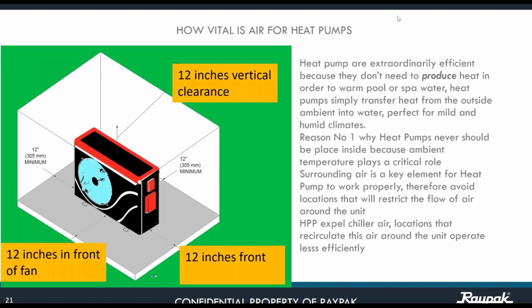Okay. On the air side, the description shown right here, guys, does not mean that the unit has to be inside of a cube, inside of a room. It's just for demonstration purposes. You need to be at least 12 inches from any wall and from the top. So basically, when you install the unit outside, and it always has to be outside, it has to be away from any wall or anything that might be preventing free airflow. You need to be 1 foot away. Remember, heat pumps are going to be extraordinarily efficient because they don't need to produce heat. They transfer heat.